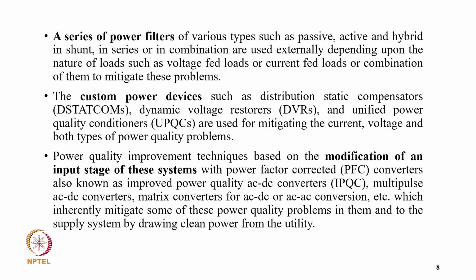So a series of power filters of various types, such as passive, active and hybrid, in shunt, in series or in combination, are used externally depending upon the nature of the loads, such as voltage fed loads or current fed loads or a combination of them, to mitigate these problems. And custom power devices such as the distribution static compensator (DSTATCOM), the dynamic voltage restorer (DVR) and UPQC are used to mitigate current, voltage and both kinds of power quality problems. So power quality improvement techniques based on modification of the input stage of these systems with power factor corrected converters, also known as improved power quality AC-DC converters, multipulse AC-DC converters, and matrix converters for AC-DC or AC-AC conversion, etc., inherently mitigate some of these power quality problems and supply the system by drawing clean power from the utility.